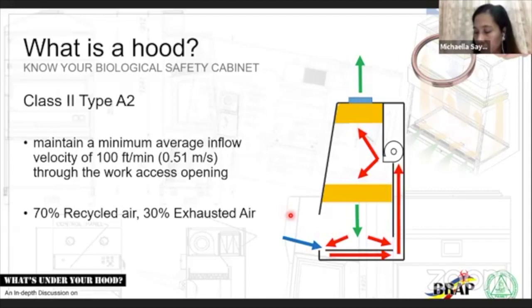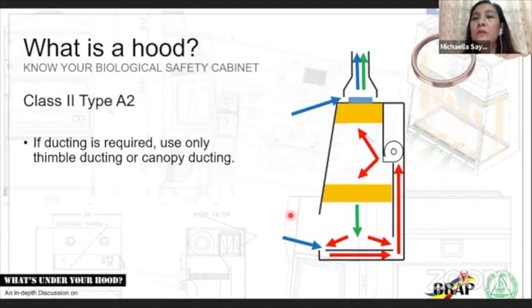So that's your class 2 type A2. Now, class 2 type A2, again, there are systems wherein you have to duct it out. So what are the conditions for ducting out your biosafety cabinet? One, if you want to exhaust room, exhaust laboratory air. And two, if you're working with volatile chemicals that are very noxious or toxic. Okay. So you would want those fumes to be ejected immediately outside of your building. So for your A2, you cannot hard duct your A2. It should be a thimble type or a canopy type.